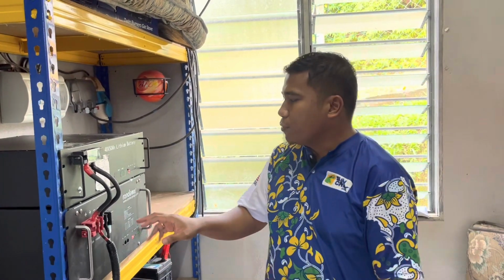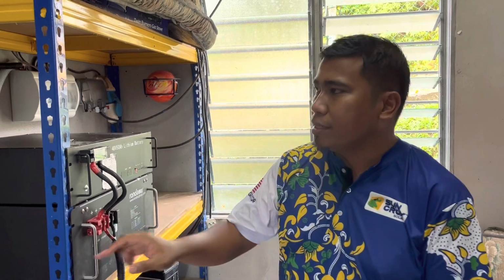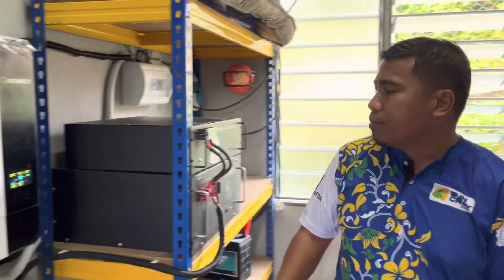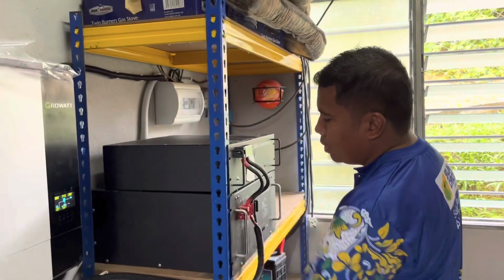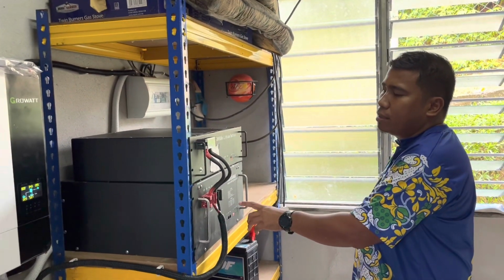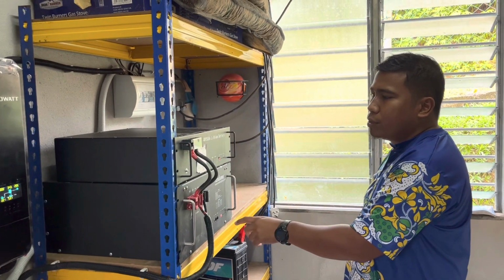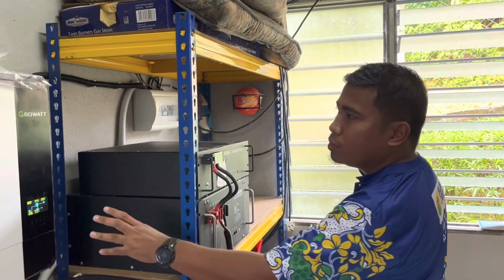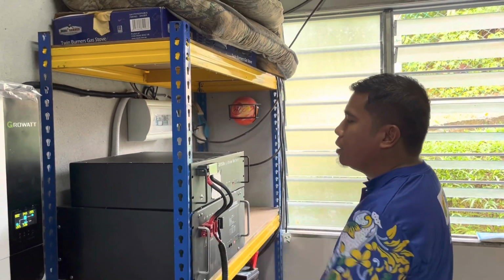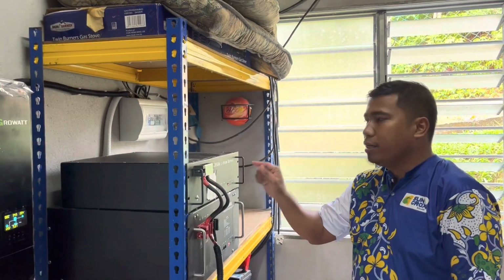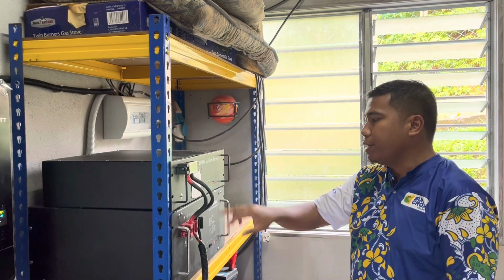Firstly we thought the 100 AH could kickstart the inverter, but this inverter is 5000 watts, and I believe the discharge rate is only 100 amps, so it's not sufficient to jumpstart the inverter. So we added another 50 AH battery, giving us 150 AH total.